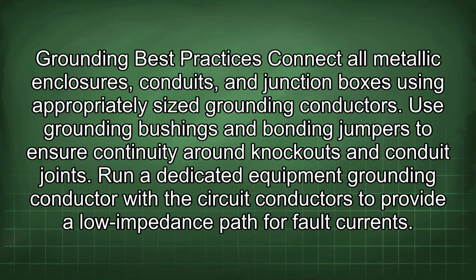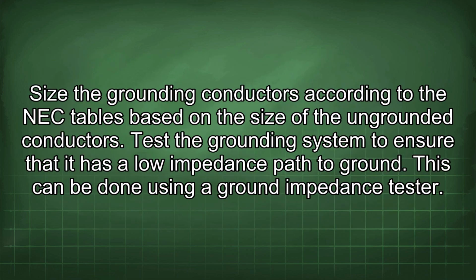Run a dedicated equipment grounding conductor with the circuit conductors to provide a low impedance path for fault currents. Size the grounding conductors according to the NEC tables based on the size of the ungrounded conductors. Test the grounding system to ensure that it has a low impedance path to ground. This can be done using a ground impedance tester.